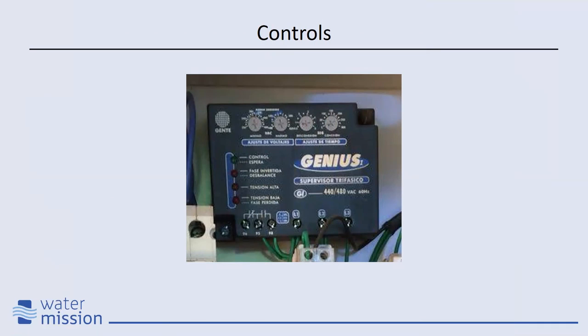That is our voltage monitor. It is a part of the control system. Voltage monitors typically are a little more complicated looking than other things, but basically we have each line of power, L1, 2, and 3, coming in to our system. We set these dials to whatever thresholds we want to act upon. And then this is the output. It either opens or closes based on if the voltage is good or bad.